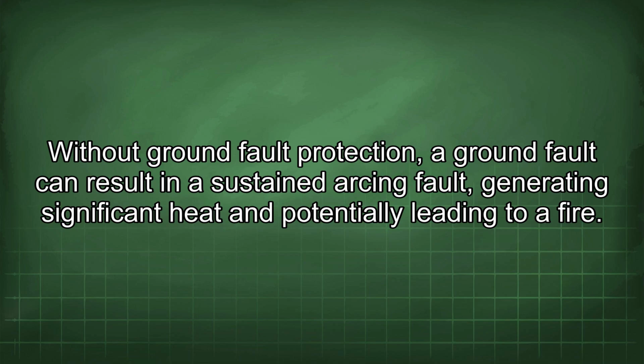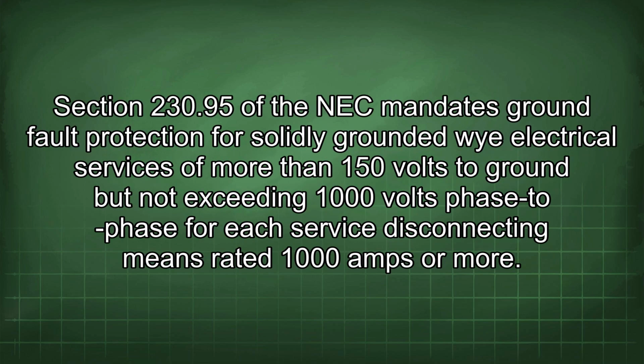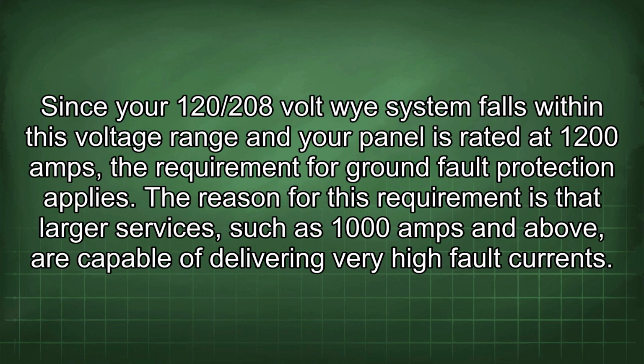to a fire. Section 230.95 of the NEC mandates ground fault protection for solidly grounded wye electrical services of more than 150 volts to ground, but not exceeding 1000 volts phase to phase, for each service disconnecting means rated 1000 amps or more.